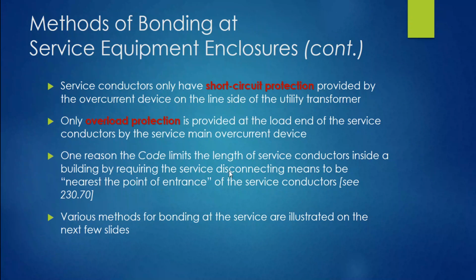Now, one reason the code limits the length of service conductors inside of a building is by requiring the service disconnecting means to be nearest the point of entry of the service conductors. Again, how we describe that in 230.70(A)(1). Again, it doesn't matter which jurisdiction you're in. Some jurisdictions let you go 3 feet. Some let those service conductors come into a building 10 feet, some 20 feet. I don't like that because that means that you have conductors inside of a raceway that are theoretically unprotected.